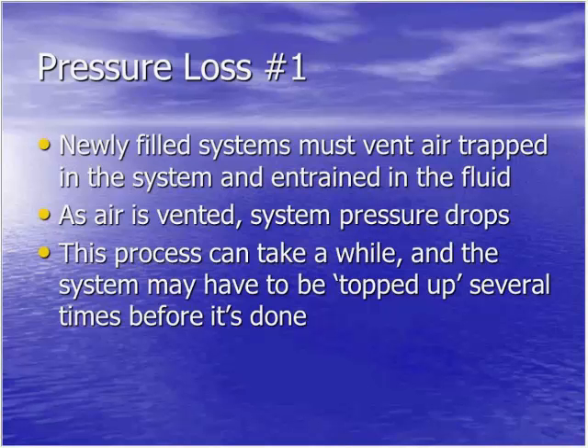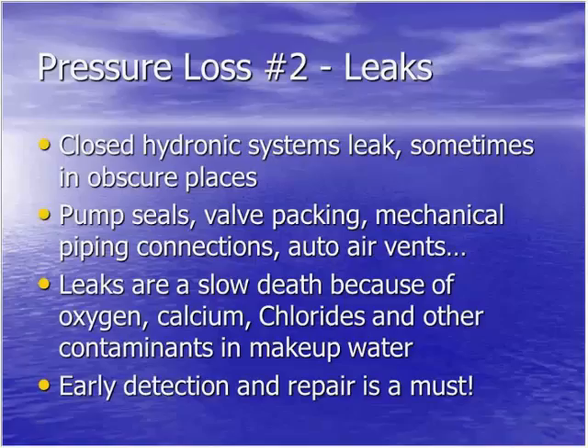Leaks. Closed hydronic systems leak, and sometimes this is in obscure places. Pump seals, valve packings, mechanical piping connections, and automatic air vents that are under negative pressure can draw air in. Leaks are a slow death because oxygen, calcium, chlorides, and all other kinds of contaminants in the makeup water make their way into the system. So early detection and repair is a must.